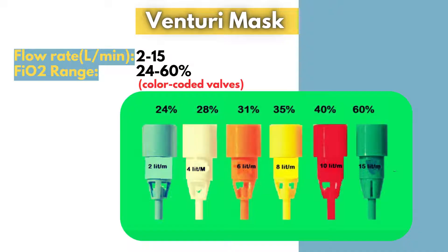The color-coded Venturi adapters deliver the following: Blue adapter — 24% at 2 liters per minute. White adapter — 28% at 4 liters per minute. Orange adapter — 31% at 6 liters per minute. Yellow adapter — 35% at 8 liters per minute. Red adapter — 40% at 10 liters per minute. Green adapter — 60% at 15 liters per minute.